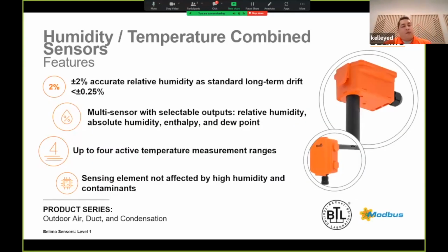All right, guys, so jumping over to the humidity side. So I mentioned this before, every one of our humidity sensors comes standard with a temperature output. Across the board, including our room sensors here on the wall, they're all plus minus 2% relative humidity accuracy.